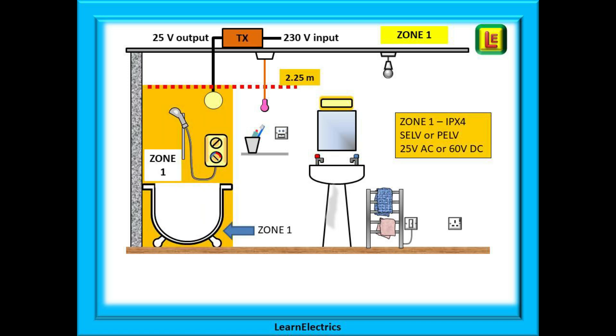Zone 1 is the standing space above the bath, from the floor up to the height of 2.25 metres. The width of Zone 1 is the width of the outside edges of the bath — not the same as the width of Zone 0, which is the inside of the bath. The area underneath the bath is also Zone 1 if the underside is open. Any equipment in Zone 1 must be IPX4 rated, including an electric shower if installed. Any lighting in this area should also be IPX4, and the voltage should be SELV or PELV, limited to 25 volts AC or 60 volts DC, with the transformer installed outside the zones.